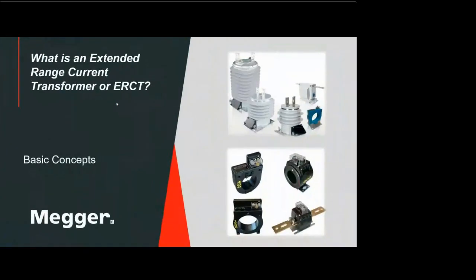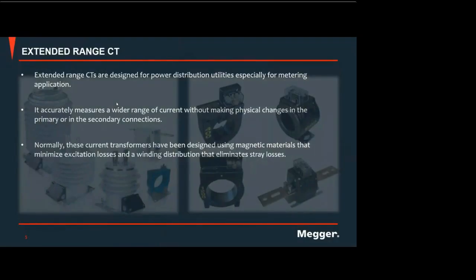Now for the agenda, of course, let me first explain what the extended range current transformer is. Extended range current transformers are designed for power distribution utilities, especially for metering applications or revenue metering. It accurately measures a wider range of current without making any physical changes in the connection. But of course, the difference with other CTs, for example the dual CTs, is that they have two ratios, meaning if they have a high current load, they will use the higher ratio, and if they have a low current load, they will use the other ratio. So that is the difference.